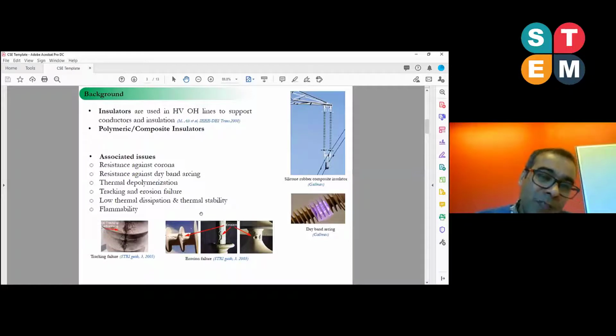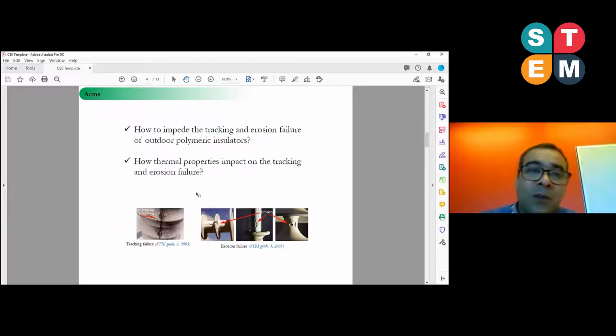So for reliable power delivery, the insulating materials must have very good erosion and tracking resistance. This work is about how we can impede that problem. The aims are how to impede the tracking and erosion failure of outdoor insulators, and how thermal properties impact tracking and erosion properties, because it's directly correlated with the leakage current amount and how much heat is accumulated on the surface of the insulator.